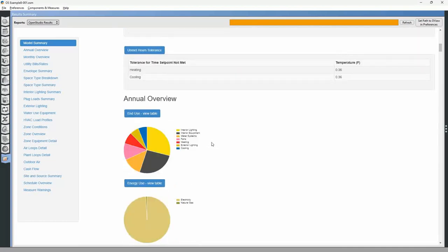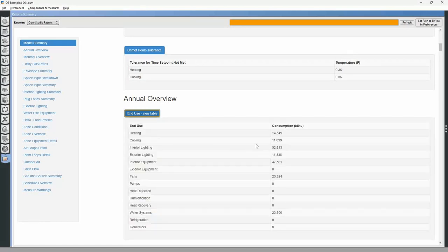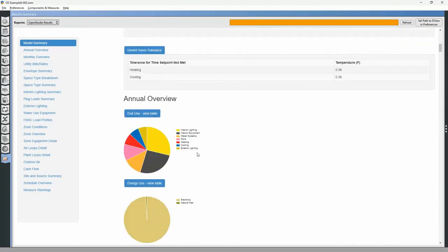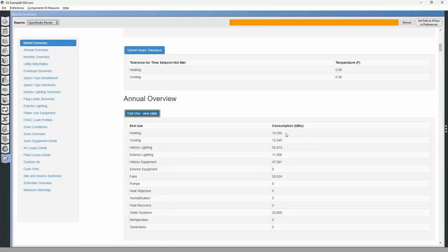Without natural ventilation, the site EUI is 33.26; with natural ventilation it is 33.04 — so natural ventilation reduced our energy use intensity. Looking at the end-use table: heating without natural ventilation is 14.350, with ventilation it is 14.549, so heating went up slightly with windows being opened. However, cooling without natural ventilation is 12.540 and with natural ventilation it dropped to about 11.100 — so cooling load went down, and there is a net savings from natural ventilation.